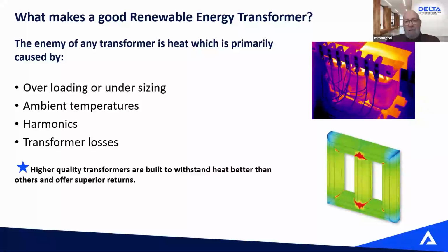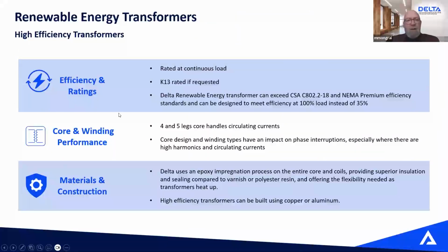So there's many things to be aware of. If you overload a transformer, the transformer is just going to overheat and you're just going to really shorten the life of your transformer. So again, when we build transformers, by regulation, by CSA, for a 75 kVA 600 120/208 transformer, the output ampacity is 208 amps. So you should be able to run this transformer at full load, drawing 208 amps all the time. The transformer is built for such. But if you run that transformer at that full load level all the time, 24 hours a day, don't expect to make 25, 30 years out of your transformer, because you run your transformer so warm that you will end up destroying your dielectric insulation system.